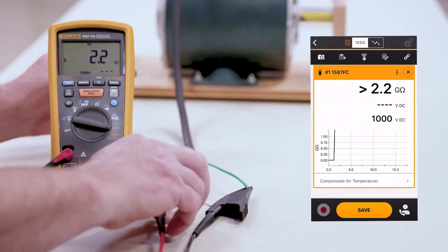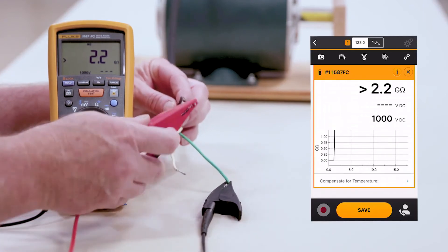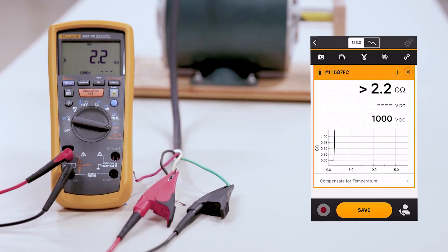Now that we're at the 1000 volt test, we're going to check the windings of our motor to ground. We're going to change the next leg by going to the black leg, as you can see here. Again, by hitting the test button, we can perform the test.